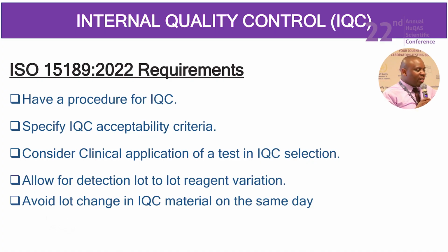Now, the criteria for IQC should be specified in that IQC procedure. We have facilities whereby we run IQC every morning, and our machines are probably automated to accept or to reject an IQC run. But when we ask ourselves, do we have our own established criteria of when do we accept an IQC run and when do we reject it? Do you want to use the Westgard multi-rule for IQC?